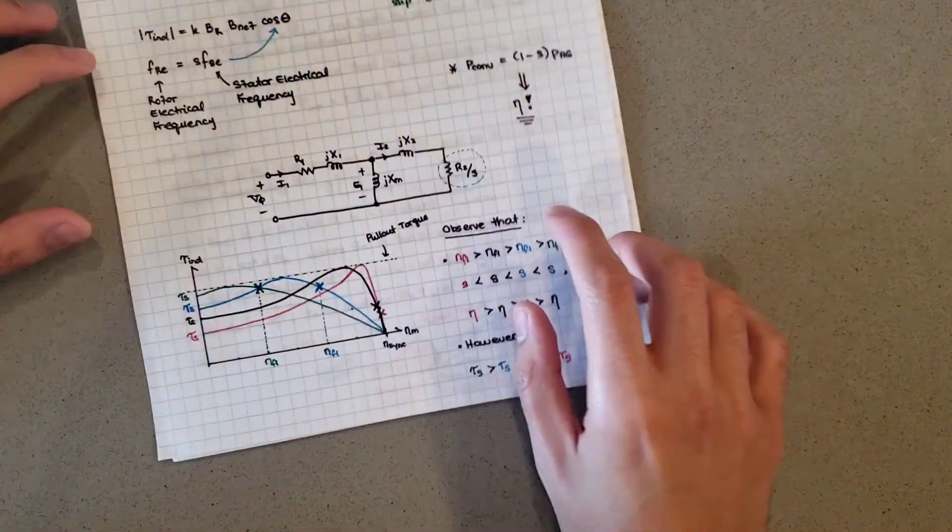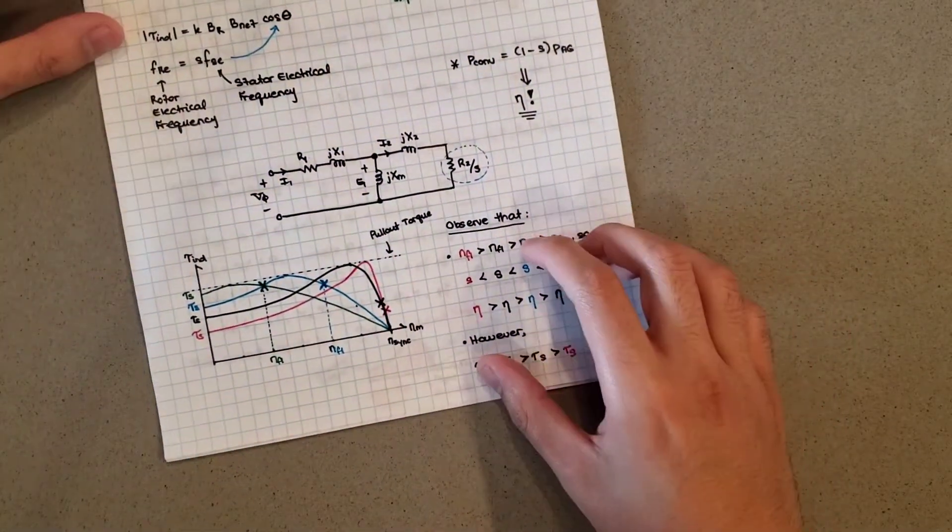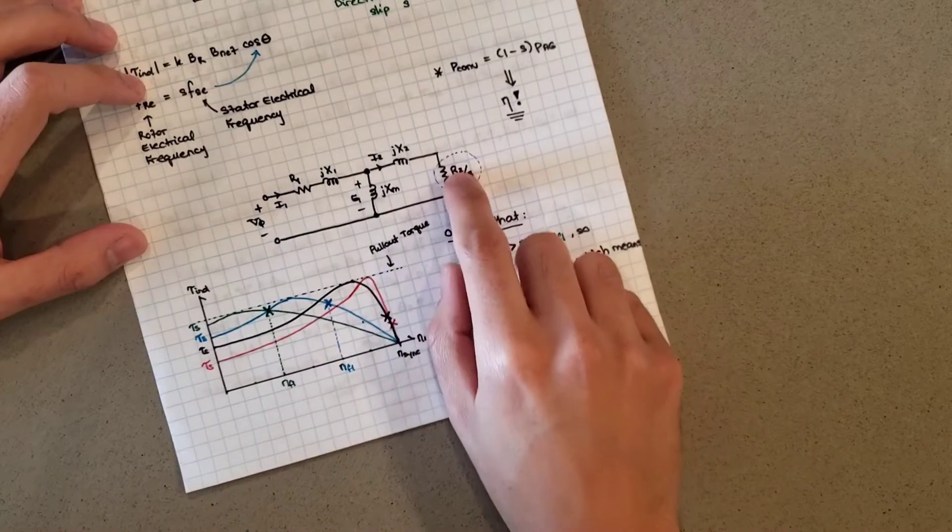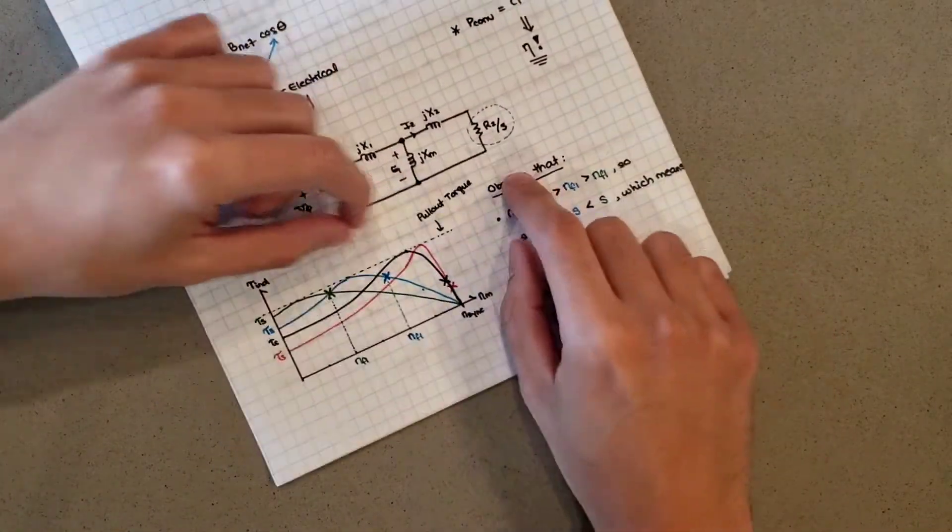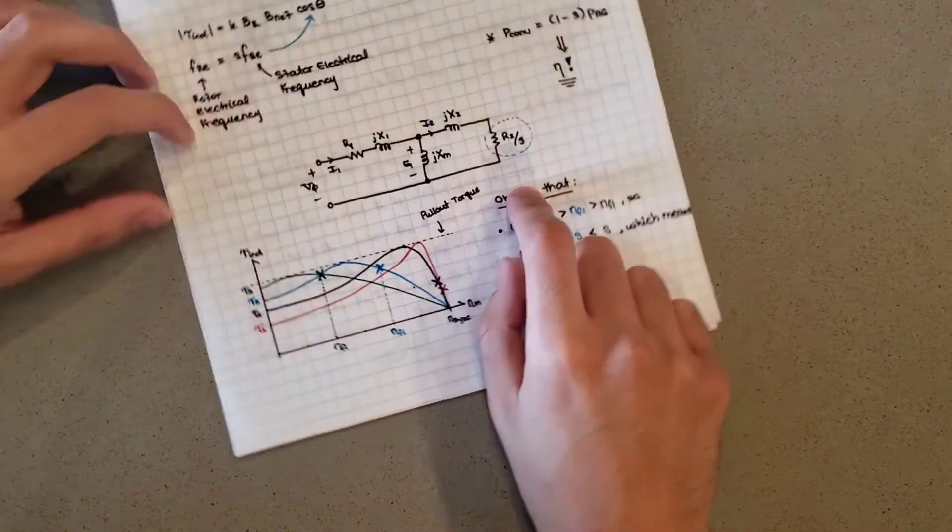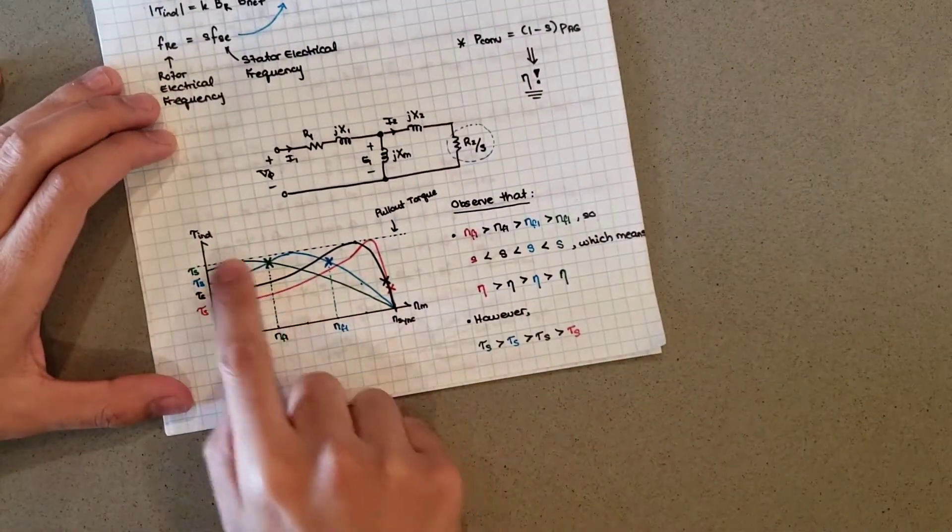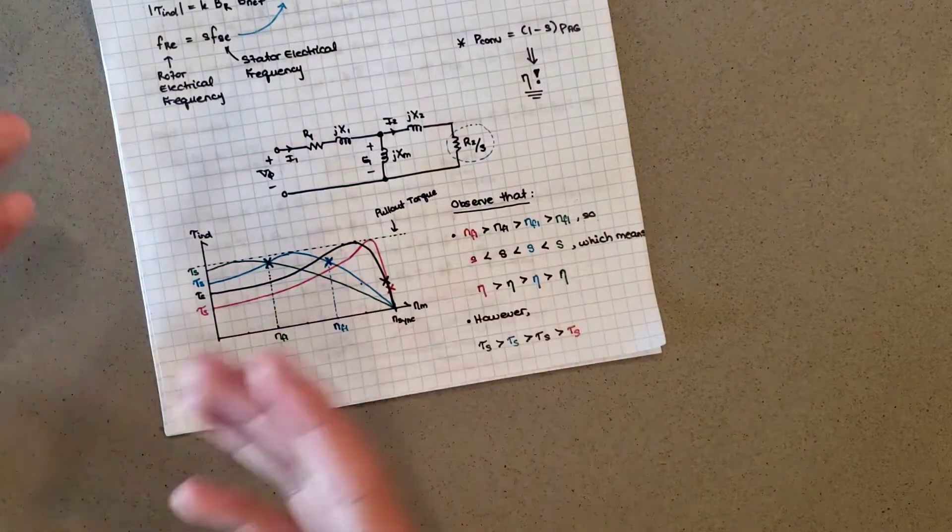Wound induction motors, by the way, make use of this. What is r2 again? r2, like I said, is the rotor coil resistance. So if I change this r2 value, I can change where the peak occurs. And remember what we said about these different curves - they have their own trade-offs, advantages, and disadvantages.